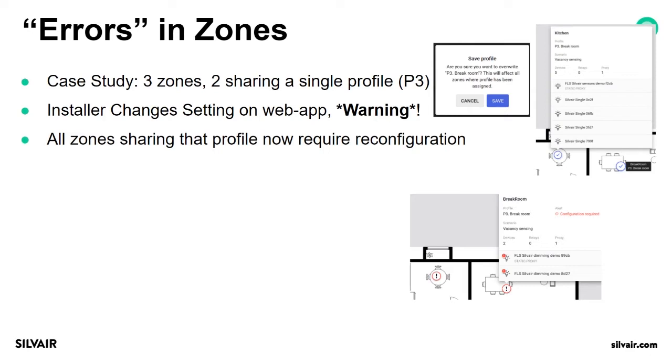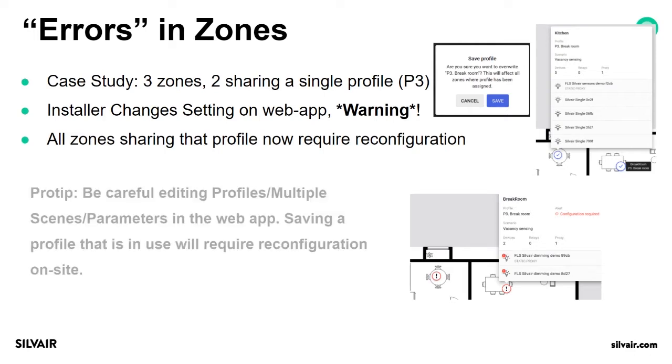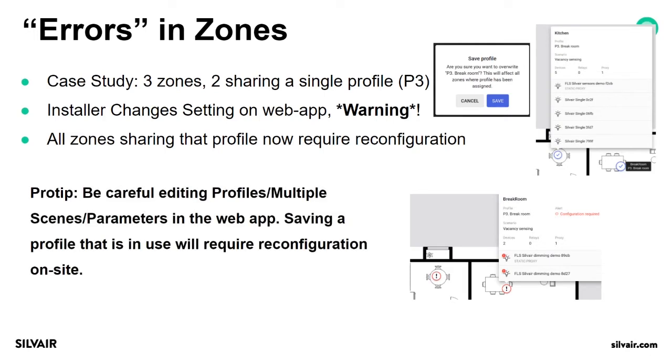We've seen examples where people are messing with profiles on the web app without notifying installers that something was changed and reconfiguration will be required. So always be careful editing profiles, multiple scenes or parameters in the web app. Saving a profile that is in use will require reconfiguration on site.